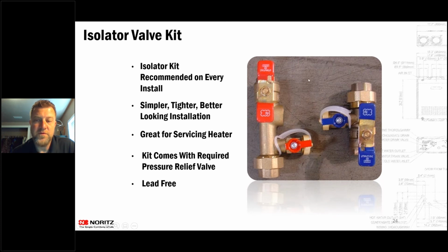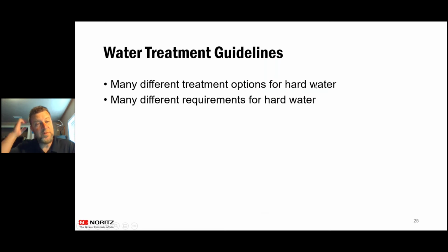All right, moving forward. So water treatment guidelines. There are many, many different water treatments out there for hard water, and many different requirements for hard water between manufacturers. So there are some tankless manufacturers out there where any hard water that runs through their unit voids their warranty, or they have different parameters. Ours is anything above 7 grains requires filtration. But we also allow either the filtration or that it's flushed once per year.